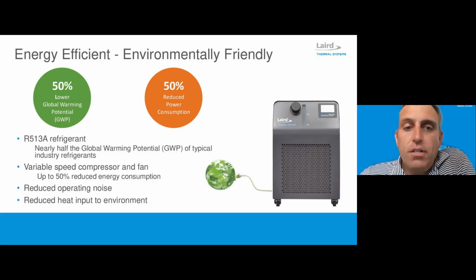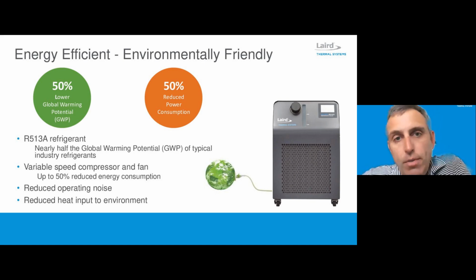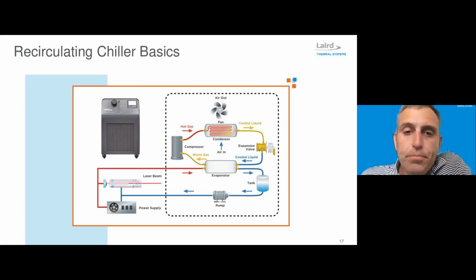So when we look at the product itself, I'd already mentioned the R513A refrigerant, very low GWP, and the variable speed motors that are used. And so this has obviously lower noise and there's some energy savings as well. But another thing that we need to keep in mind is the impact on the installed site. With us consuming less energy, it also means we're rejecting less heat into the environment. And so this has a lower impact on the HVAC system of which the chiller is installed.